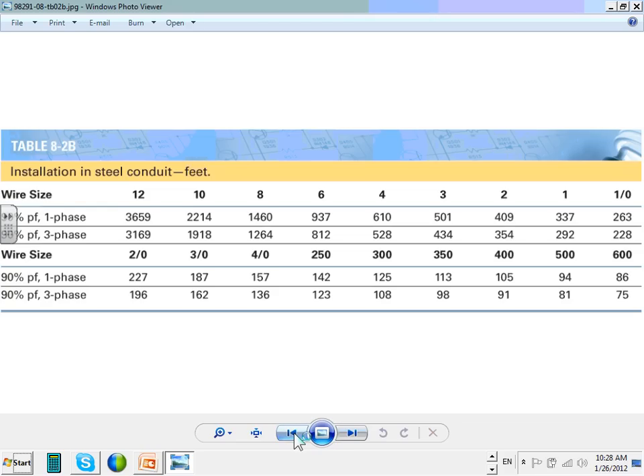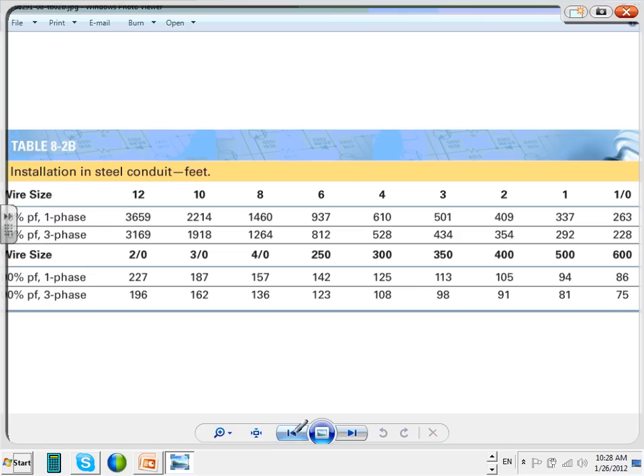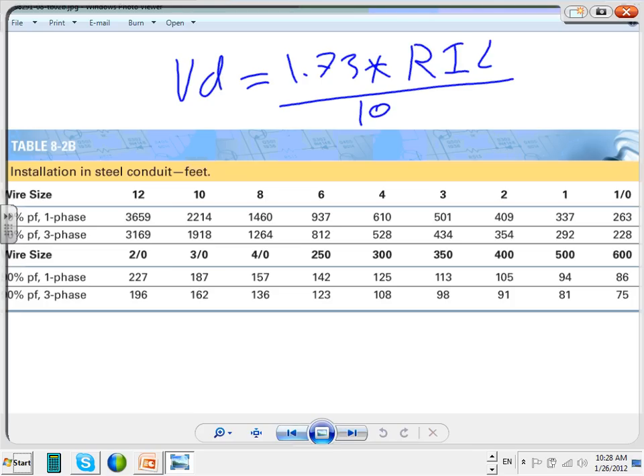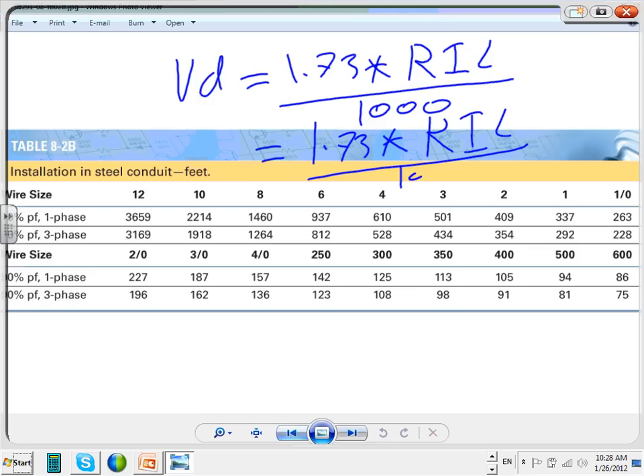If you go to 1-22, it'll give you the formulas you need to find voltage drop: 1.73 times R times I times L over 1,000, or you can use the scale 1.73 times K times I times L over 1,000. These are the rules we use, guys, to calculate the voltage drop for a three-phase system, and we are dealing with a three-phase system. And this is on page 1-23.